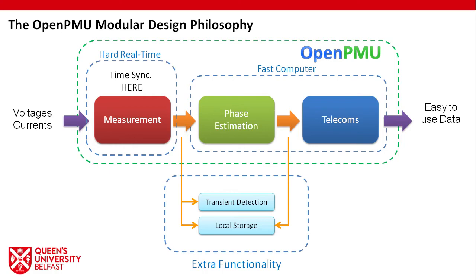This module has functions which do transient detection, and in the case that they detect a transient, will save the sampled value data and indeed perhaps the synchrophasor data to local storage. It's very important to note that this is extra functionality above and beyond what a PMU is required to do, and the IEEE standard C37118.1 only describes PMU function, not any of the other functions within a multifunction device incorporating a PMU.